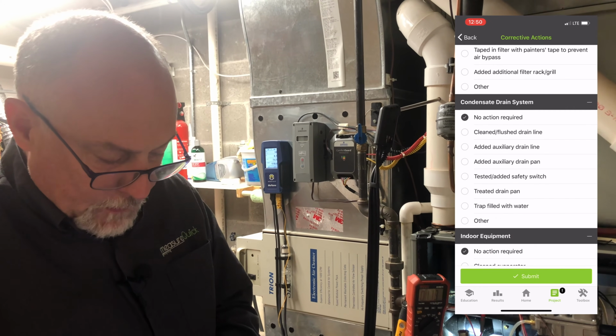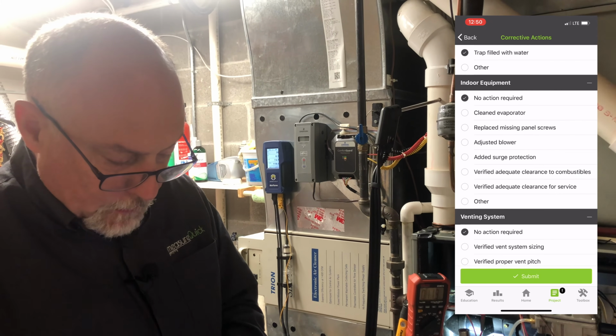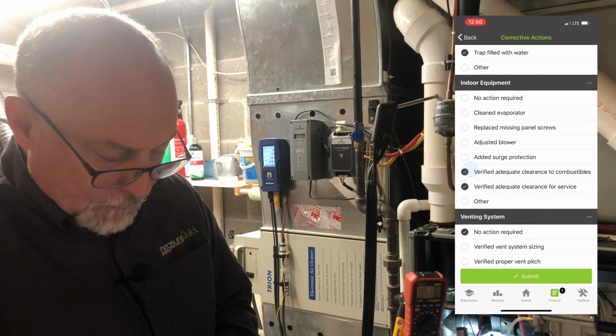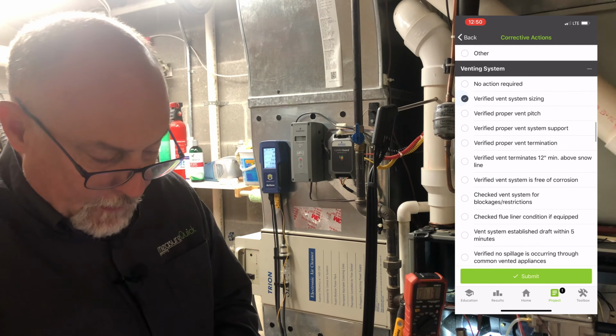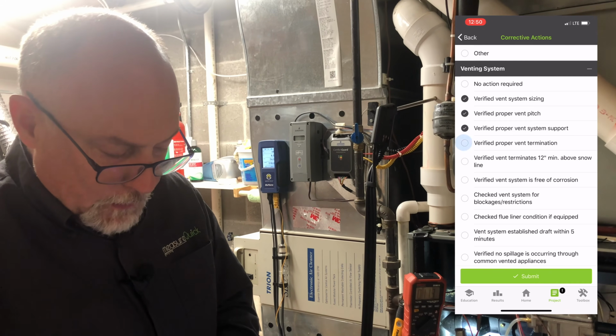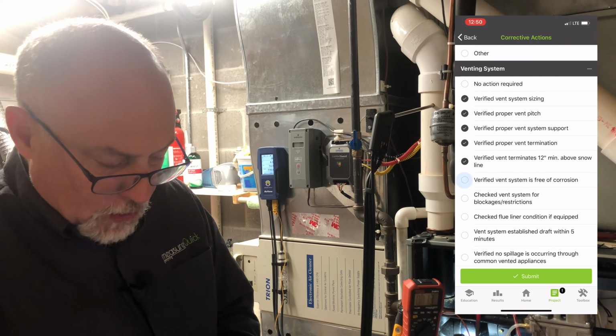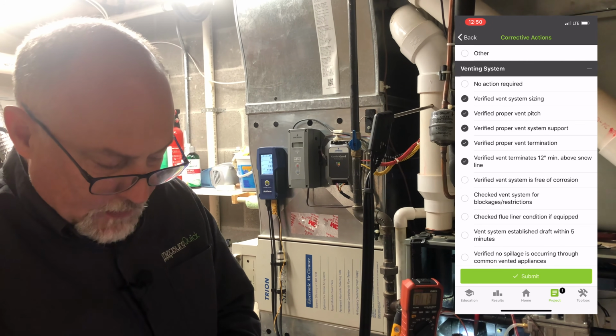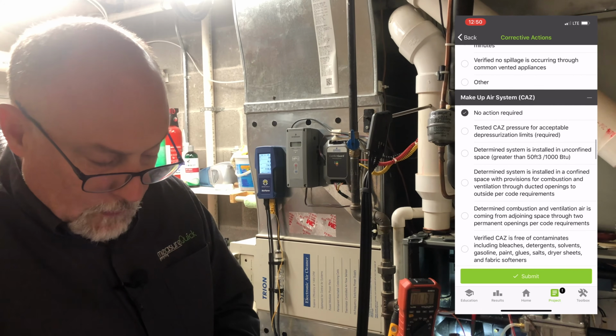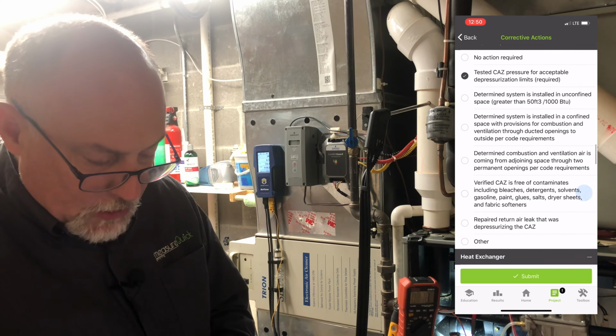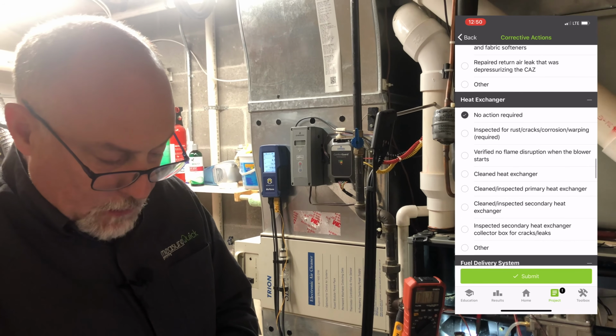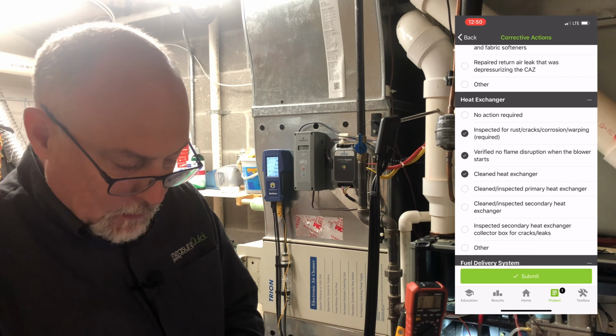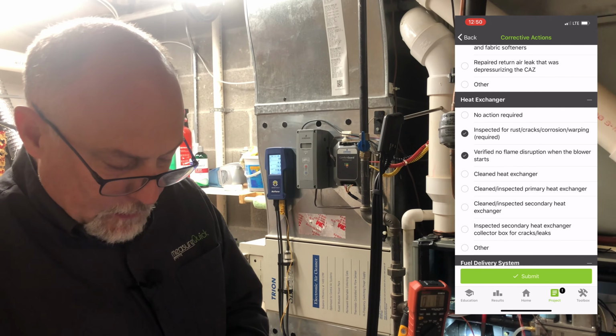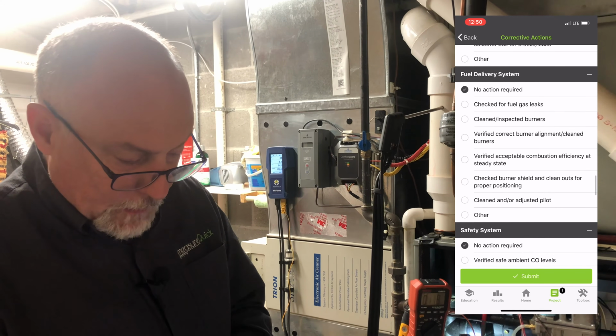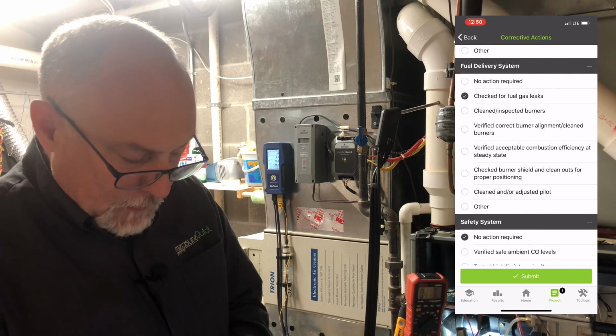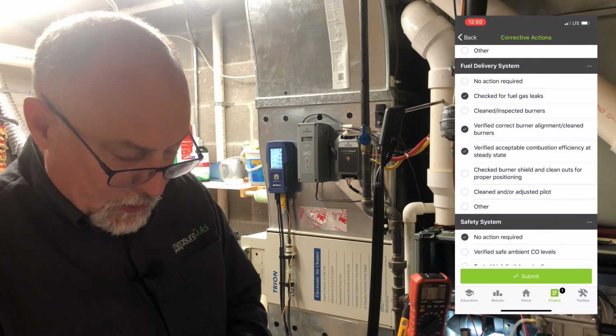Condensate drain, we did fill the trap with water, and then let's see here, verified adequate clearance to service and combustibles, so that was good. Venting system, we verified proper size, pitch, support, termination, verified it's 12 inches above the snow, verified that there's no vent system blockages. And then our CAZ, we did test it for acceptable depressurization limits. And also on our heat exchanger, we verified there's no flame disruption, no cracks. And then we inspected the secondary. Fuel delivery, we did check for fuel gas leaks and verified burner alignment, verified combustion.